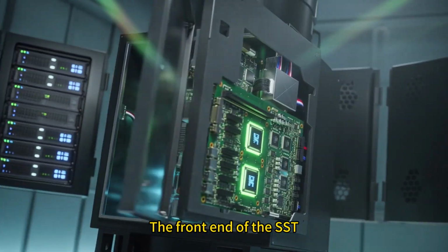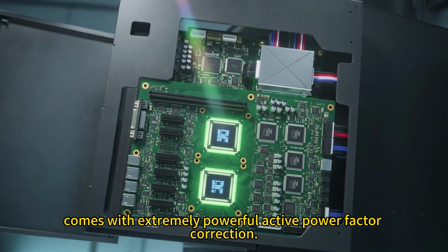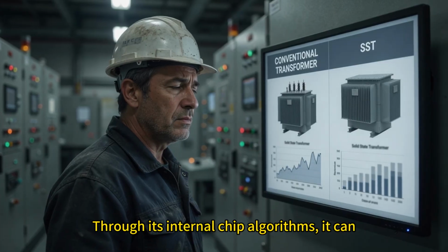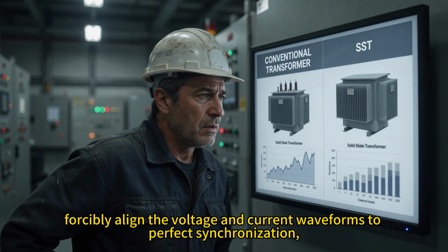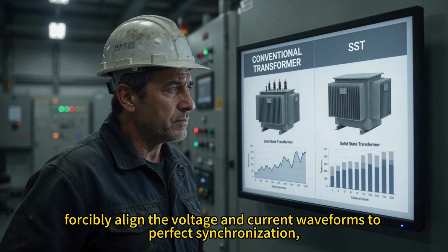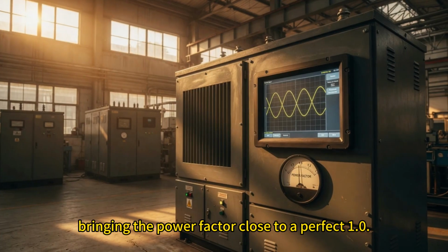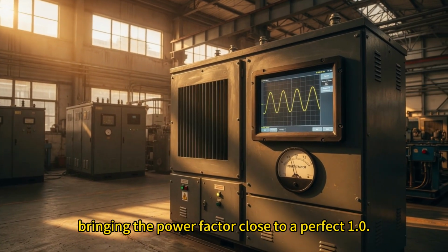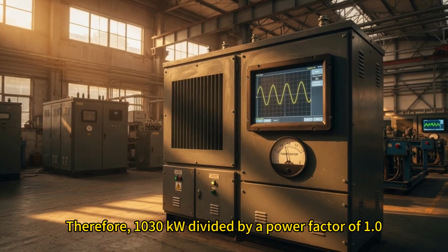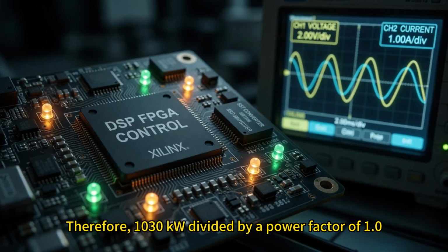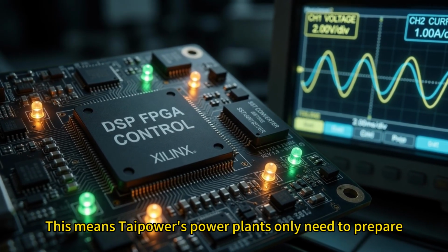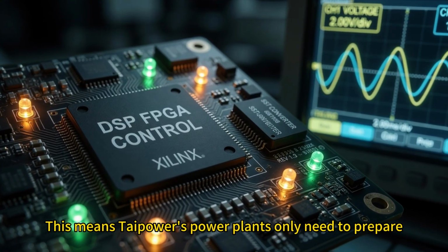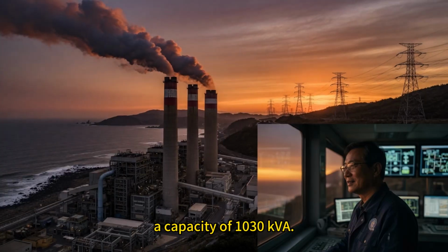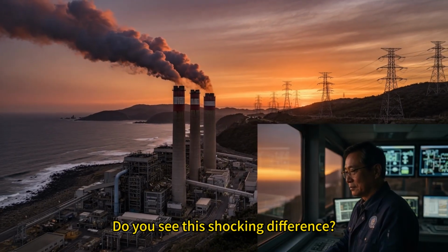The front end of the SST comes with extremely powerful active power factor correction. Through its internal chip algorithms, it can forcibly align the voltage and current waveforms to perfect synchronization, bringing the power factor close to a perfect 1.0. Therefore, 1030 kilowatts divided by a power factor of 1.0 equals 1030. This means Taipower's power plants only need to prepare a capacity of 1030 kVA. Do you see this shocking difference?